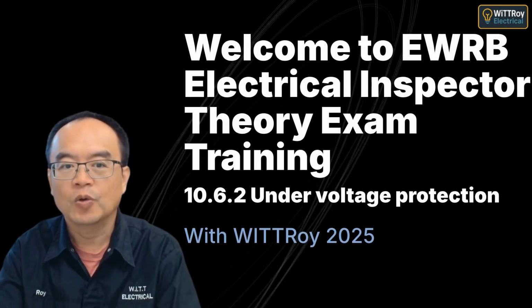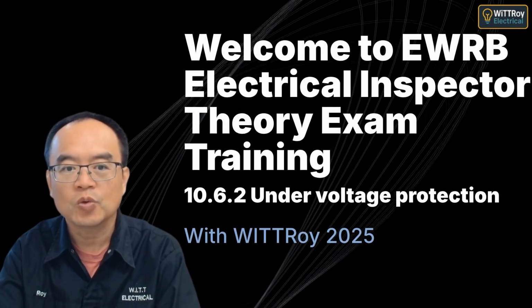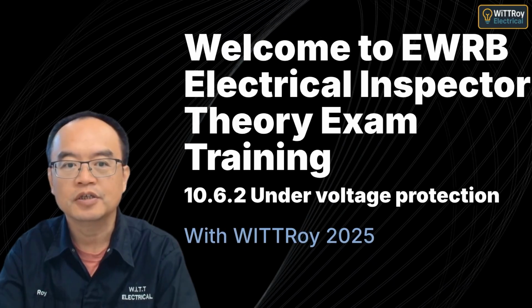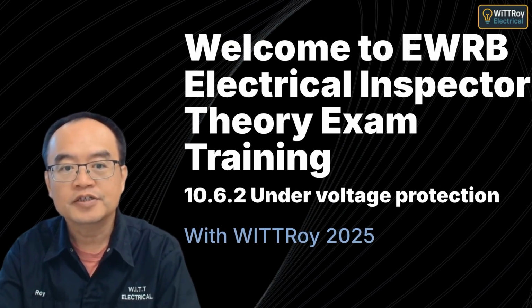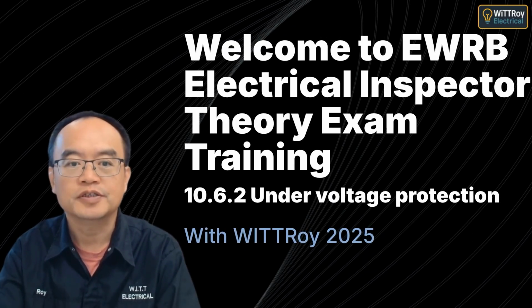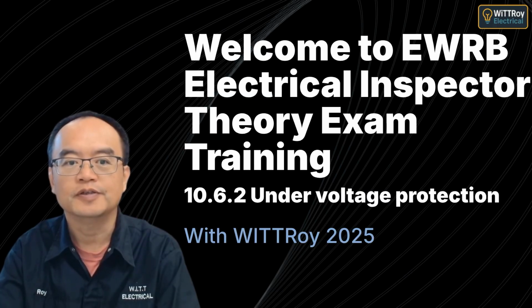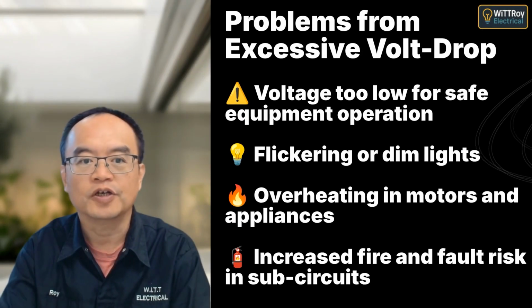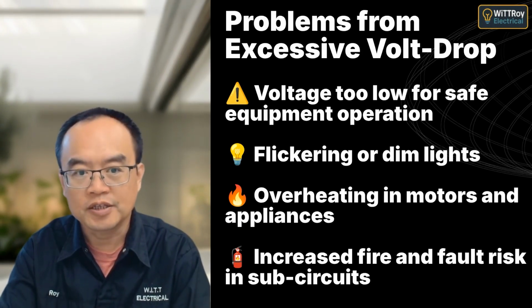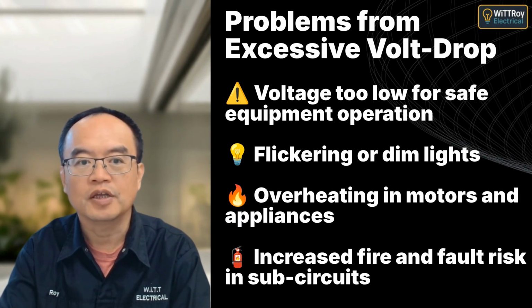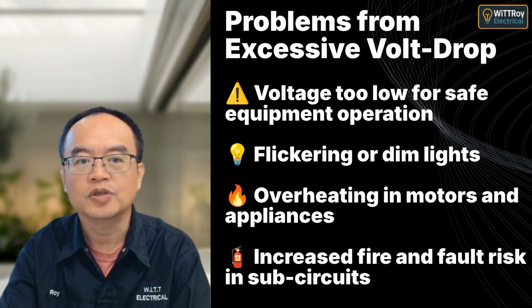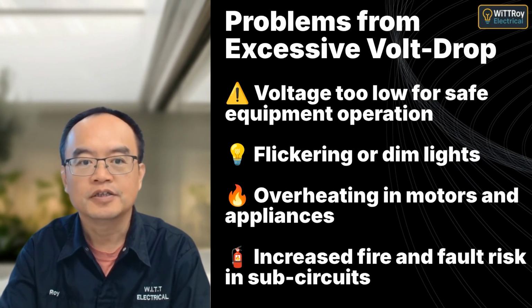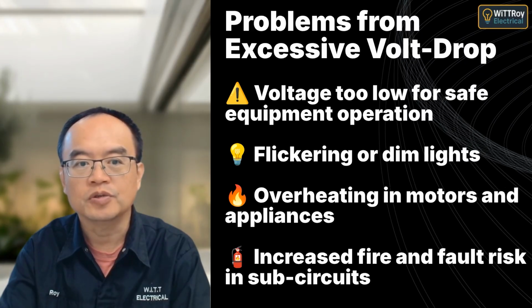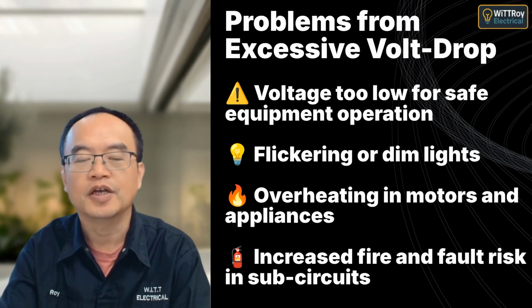Hi everyone, I'm WITTRoy. In this short lesson, we're talking about undervoltage protection, what problems it causes in installations, and how to choose the right protective devices to prevent damage and instability. Too much voltage drop in an installation can cause lights to flicker, motors to overheat, and appliances to fail. It also leads to serious risks in minor circuits, especially where long cable runs are used. Managing this is part of good electrical design.